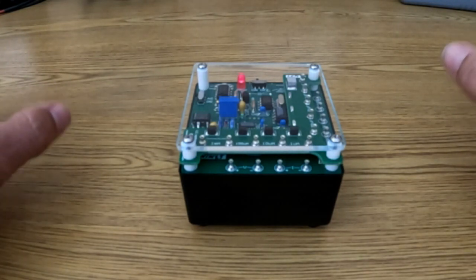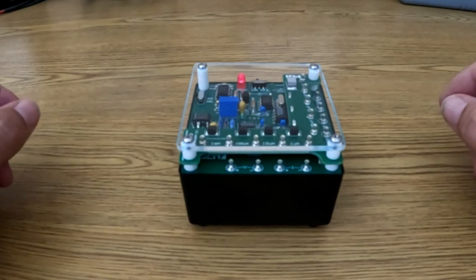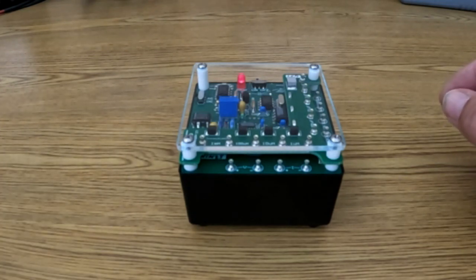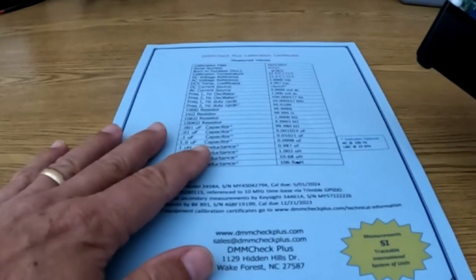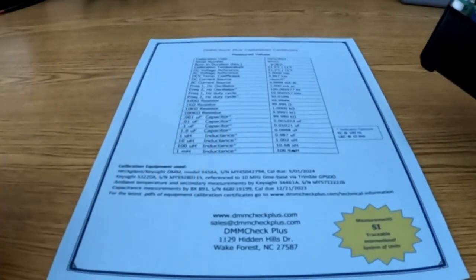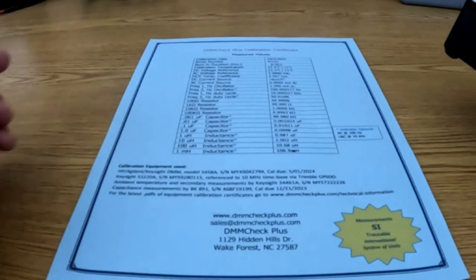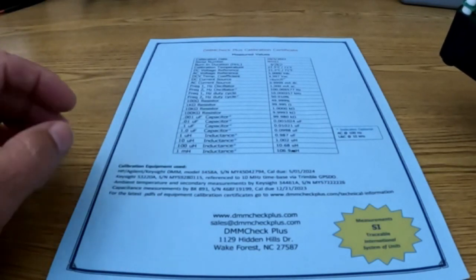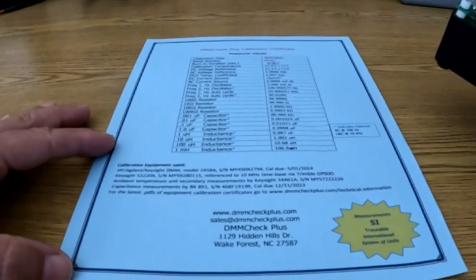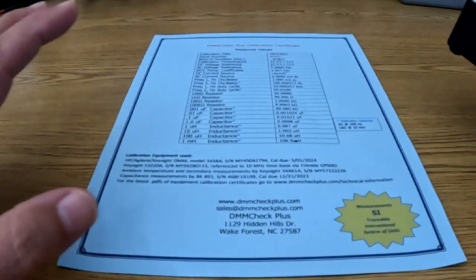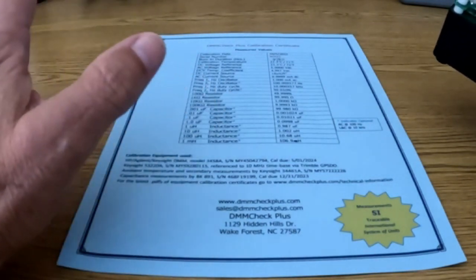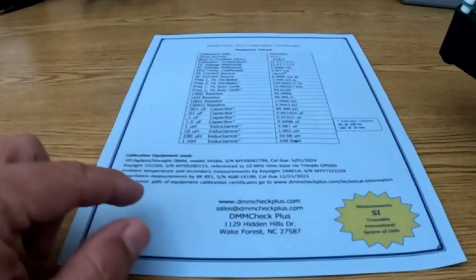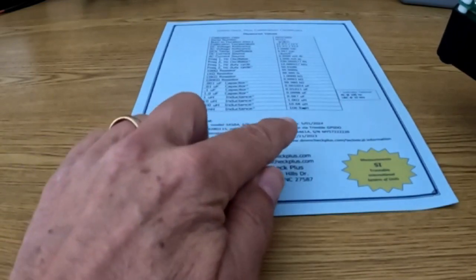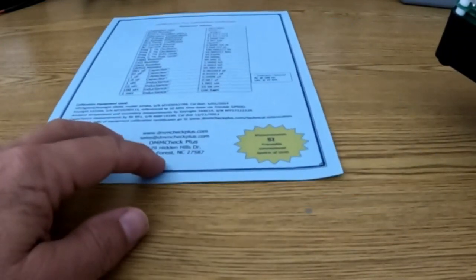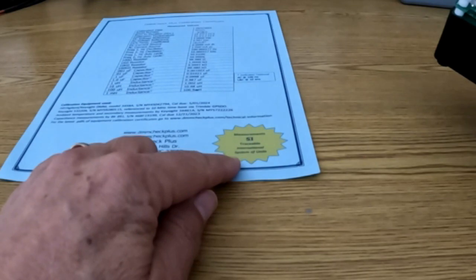So I was looking for an in-house reference standard with some sort of calibration certificate I could show to the inspector for UL and ETL. We had to have something like this when I worked in avionics. They would come back every year and check our airworthiness certificates, and they wanted to see how our equipment was calibrated, what it was calibrated on, its due dates, and that it had traceability.